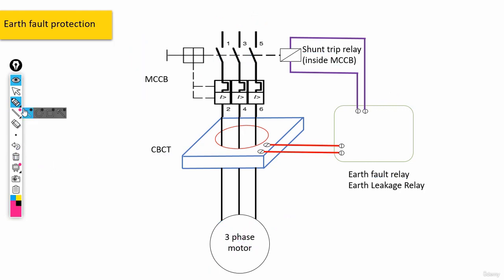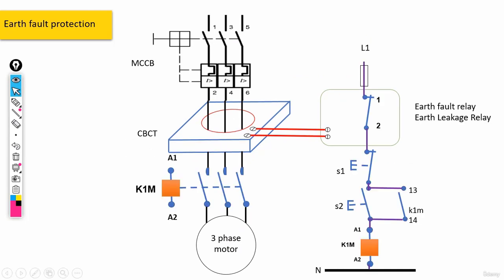Now, guys, we are also able to do something else. Let me change the slide. Okay, guys, take a look at this diagram. The thing is, sometimes inside the relays, we would find a normally closed contact, like this. All right, now, once again, the three phases L1, 2, and 3 would move through the MCCB breaker, and then they would enter the CBCT transformer right in the middle again. Then they would be connected to the contactor, and from the contactor to the motor.